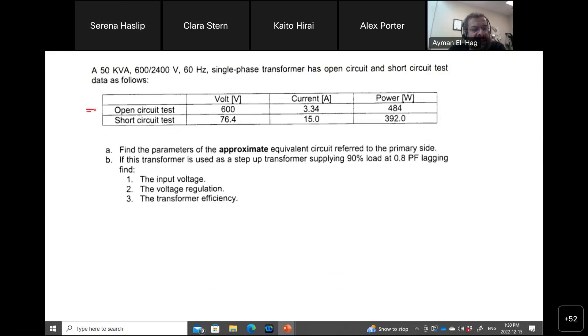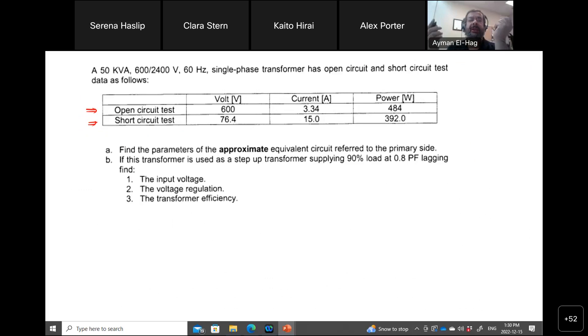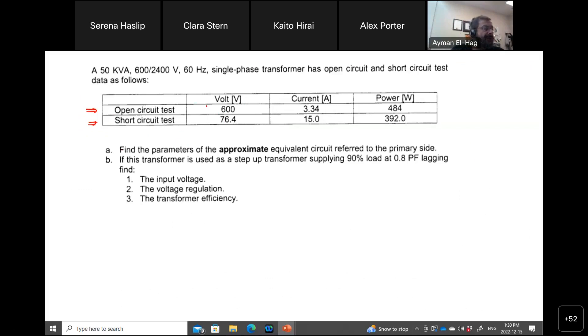This is your open circuit test and this is your short circuit test. For the open circuit test, we always apply the rated voltage — meaning I apply the maximum voltage to one side and leave the other side as an open circuit. Here it's very clear that I apply 600 volts, and the transformer is 600 by 2400, so I am applying values from the primary side because this is a step-up transformer.